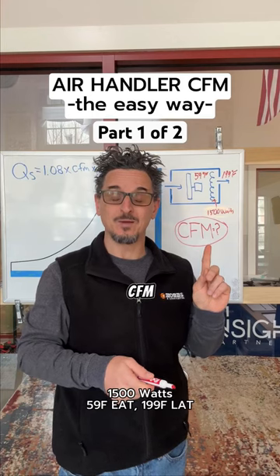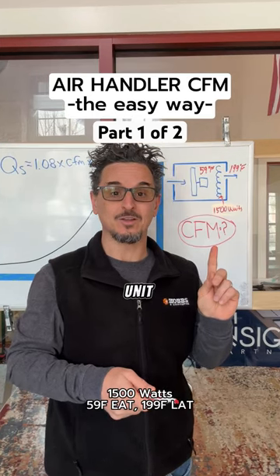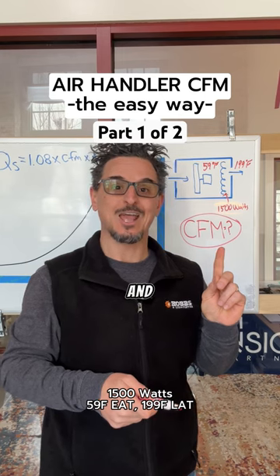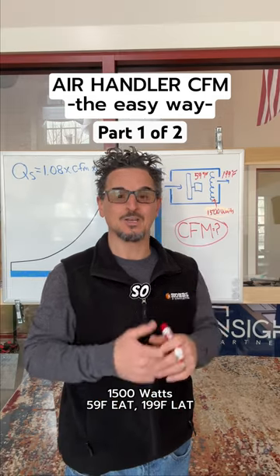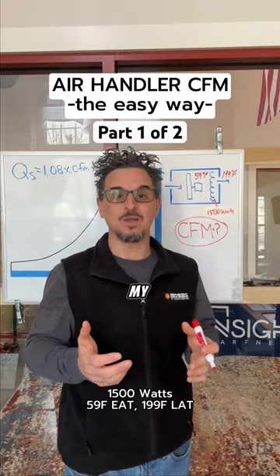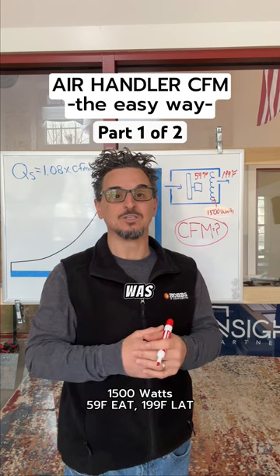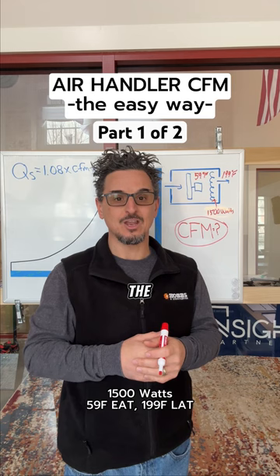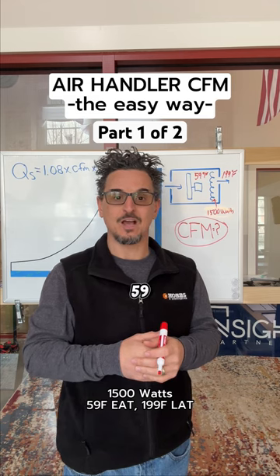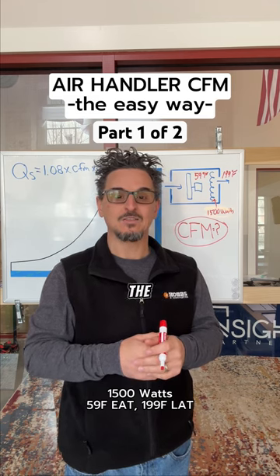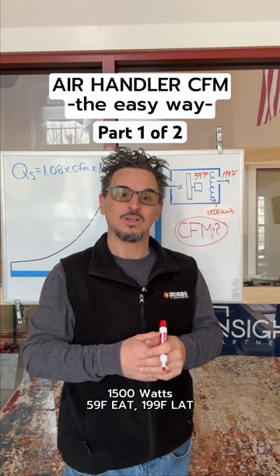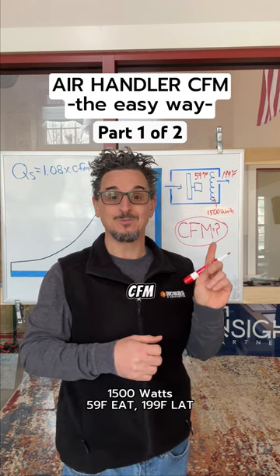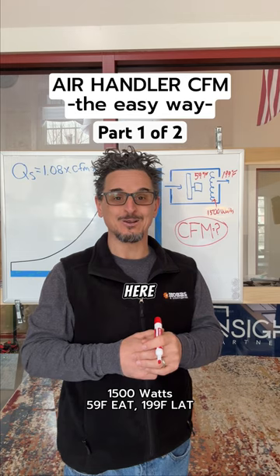Did you know you can calculate the CFM of any air handling unit, provided you know the electric heater KW and the Delta T across that heater? Yesterday we looked at the smaller unit heater in my basement, which was a 1500-watt heater. The air entering the heating coil is 59 degrees and leaving the heating coil is 199 degrees. How many CFM was that fan doing on the unit heater?